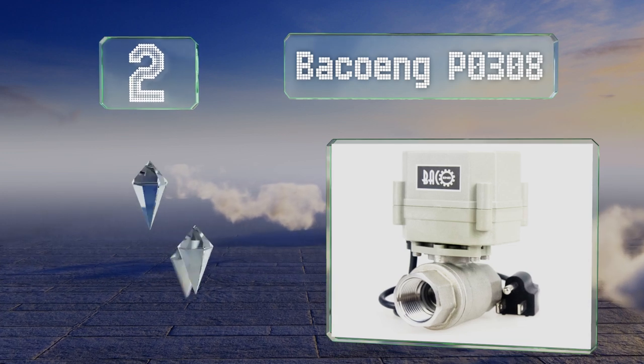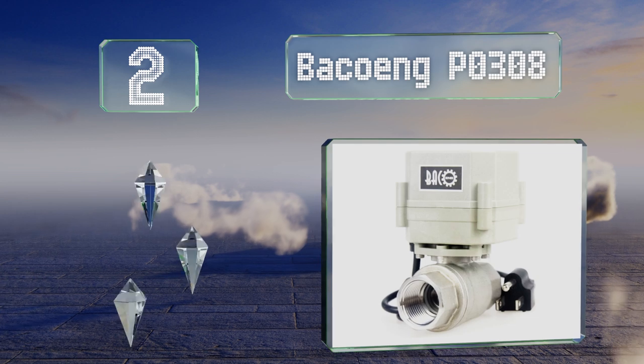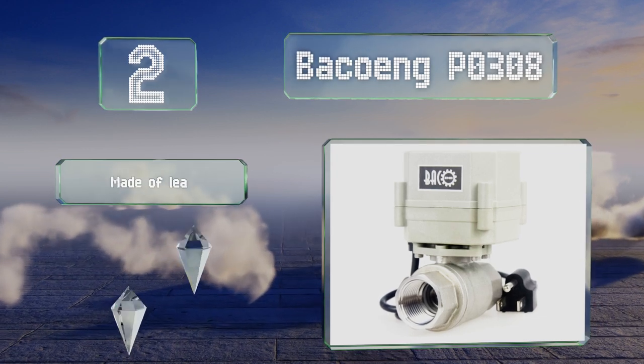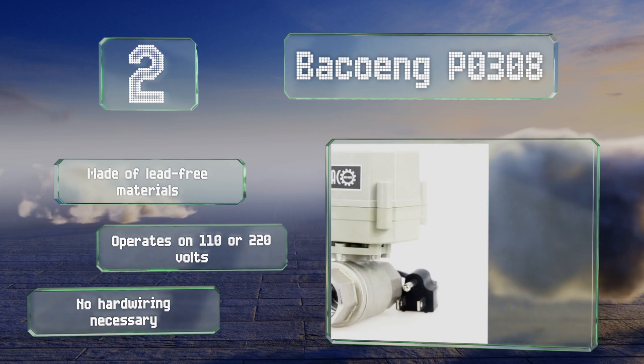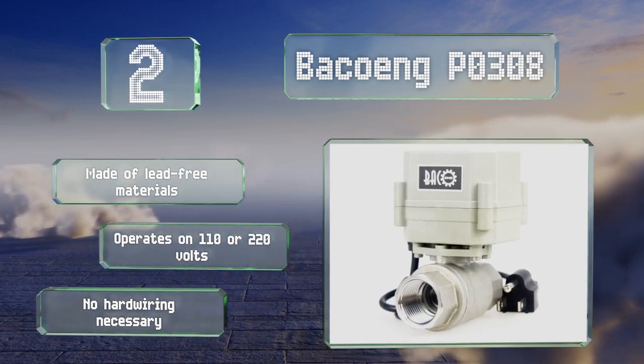At number 2, although the Bacoeng P0308 is described as having spring return functionality, in reality an integral battery pack is responsible for restoring it to its closed state upon cutting the power. In this manner, the utility it offers is similar to that of a solenoid valve. It's made of lead-free materials, operates on 110 or 220 volts, and no hard wiring is necessary.